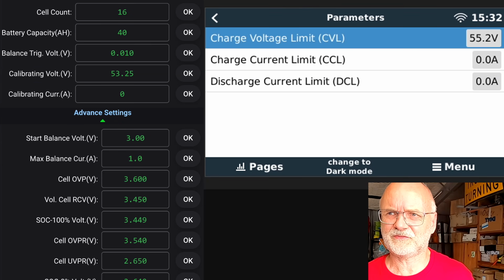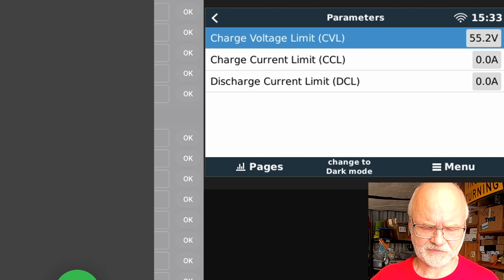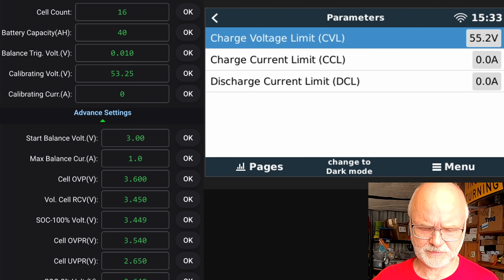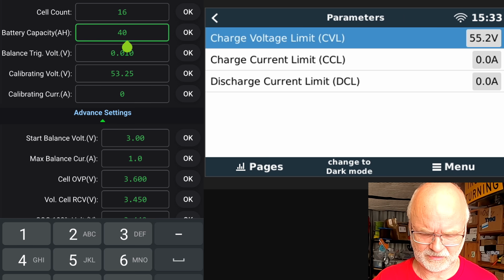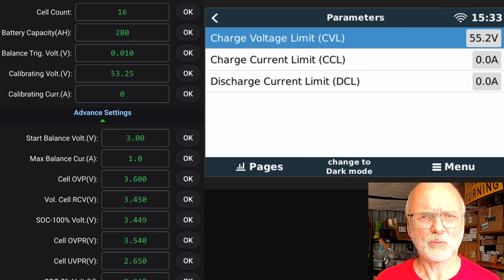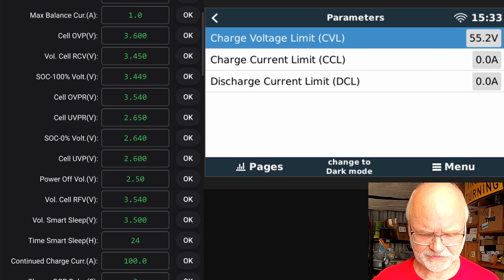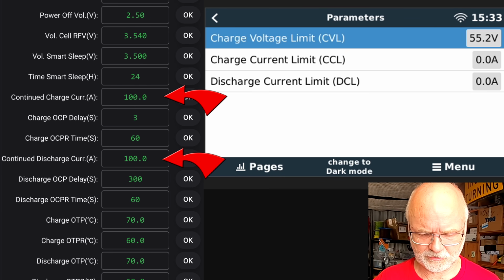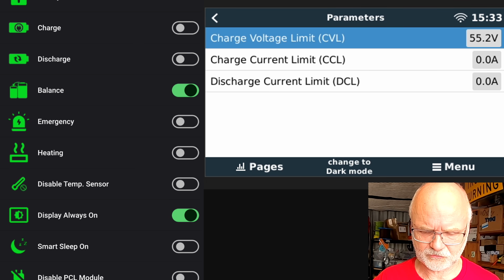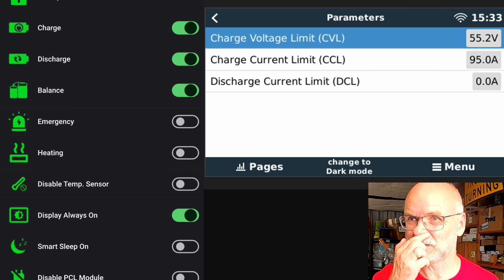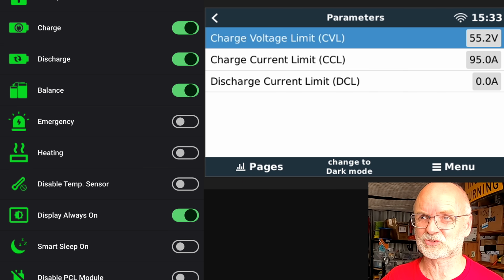Okay, let's check out the CCL and DCL functions as well. So let's log back into our master BMS. Why has the master BMS again 40 ampere hours sitting here? 280, okay. Why has it fallen back to 40? So we just check the continued charge current 100, discharge current 100 amps. Go into controls and turn on charge, turn on discharge. And we should see the 95 amps showing for both, because it keeps 5% as a margin.